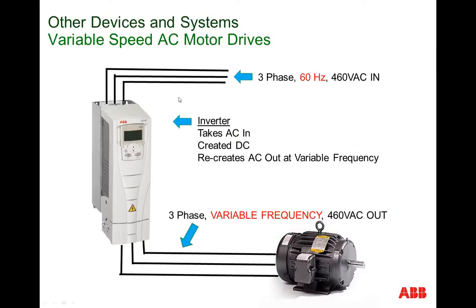Now, we mentioned at the outset that 60 hertz electricity is prevalent and that an AC motor is a 60 hertz machine. Well, not quite. In recent years, there's a new technology out called a variable speed AC motor drive. What happens is this is an electronic box wherein we will feed three-phase 60 hertz electricity at 460 volts into what's known as the AC drive.